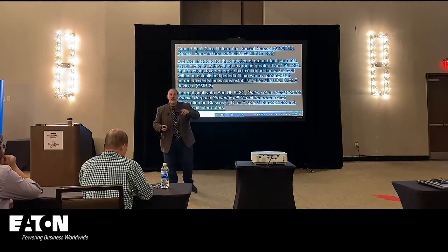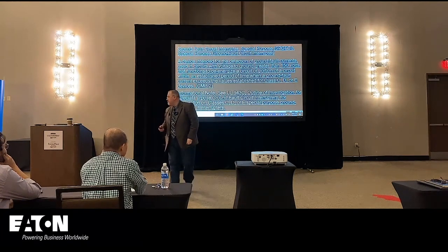In Europe, they don't care about the let-go, they worry about the defib, okay? And the 30 milliamps is because of those accumulated leakage currents. In some cases, some countries use 300 milliamps at the main. So they put 300 milliamps at the main on a structure, and then 30 milliamps on the branch circuits.